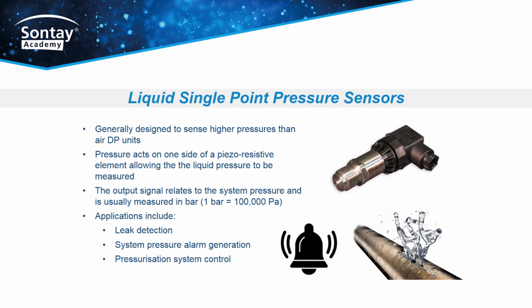Single-point pressure sensing in a liquid system can be suited to general alarms for under or over pressure events, as well as control pressurization of the system. A common use for pressure sensors is for leak detection, where a sudden or sustained drop in pressure might indicate a leak. Sensing mains incoming pressure allows the building owner to monitor the status of the utility supply to the building.